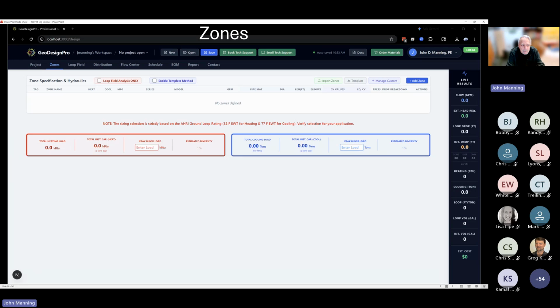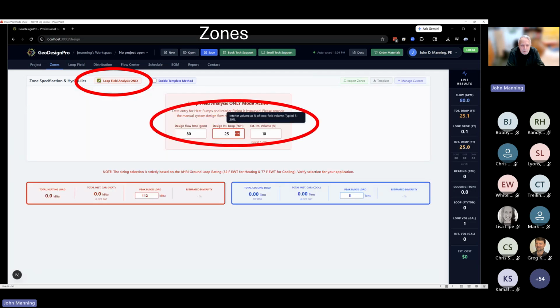But if you don't want to take the time to define all your zones at this point in your process, there's an option to just analyze the loop field. So you check that box and a new window pops up where you get to specify a flow rate that you're designing to. And you put a placeholder in for your internal part of your system pressure drop. In this case, we said 25 feet of head. You put a percent of volume that might be in the interior piping.